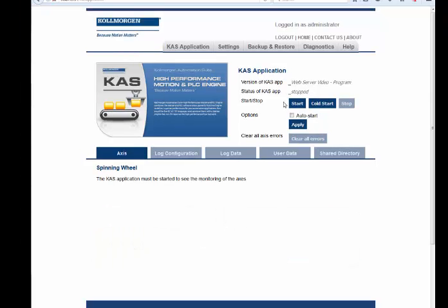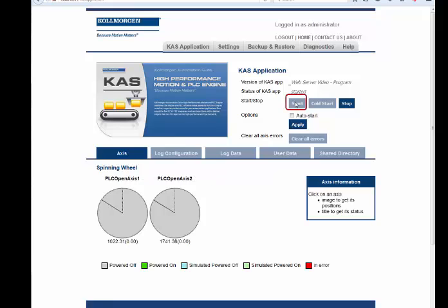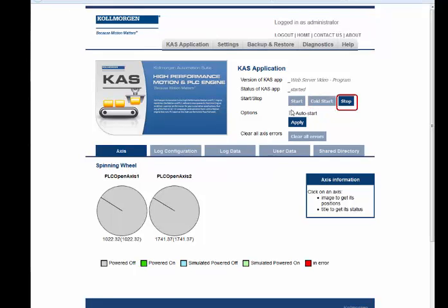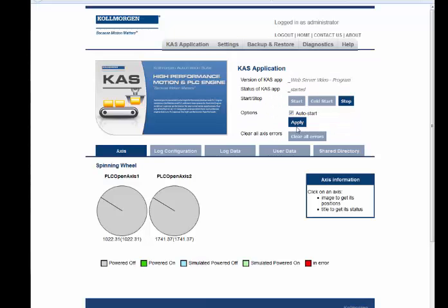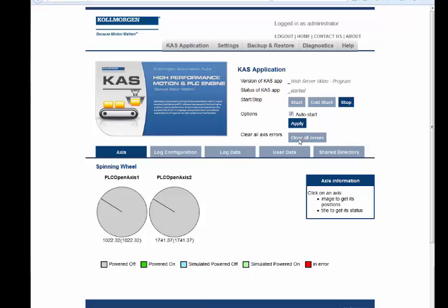In the KAS Application tab, the Axis sub tab can be used to start, cold start, which will additionally reset all retained variables to their initial values, or stop an application. Clicking on auto start, then apply causes the application to start automatically when 24 volts is applied to the controller.